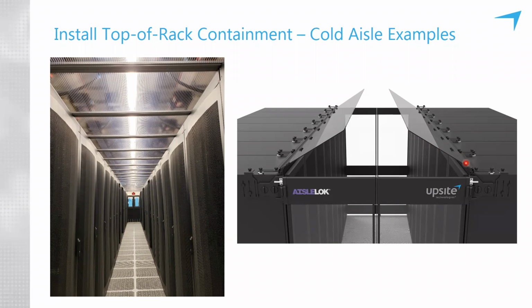And they attach magnetically, completely toollessly. You can see at the back of each baffle, those silver elements are cup magnets. These come out of the box and you tilt them into place and the magnets attach. One of the great benefits is that they are removable. So if there are cable trays or a need to access the tops of the cabinets, these can easily be removed and then replaced. And you may be wondering, how does an open top containment work? I'll cover that in just a moment as I talk about some of the science of airflow management.